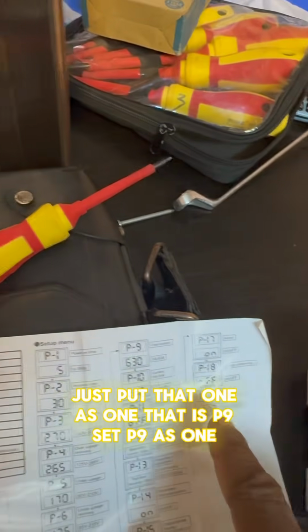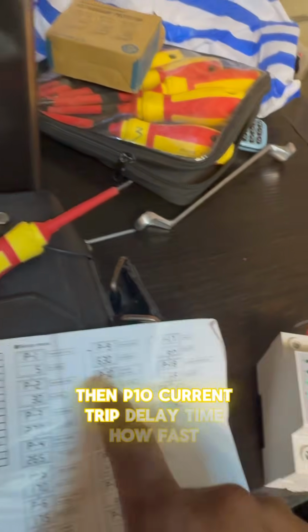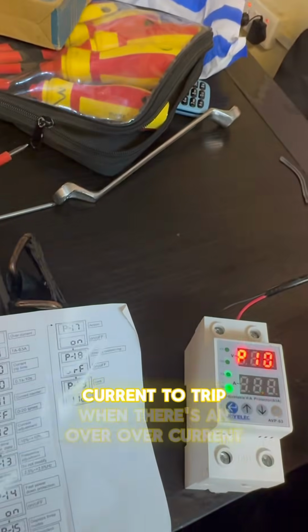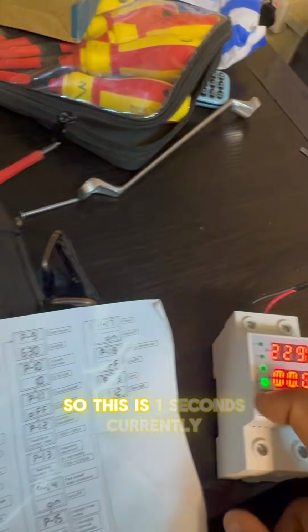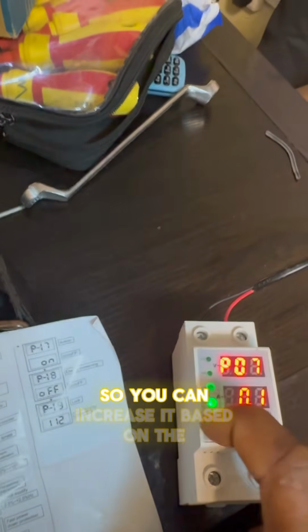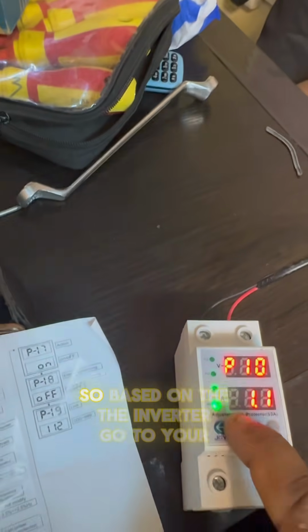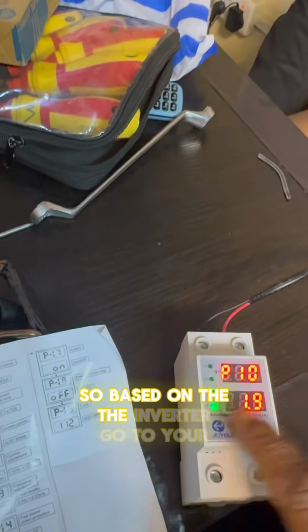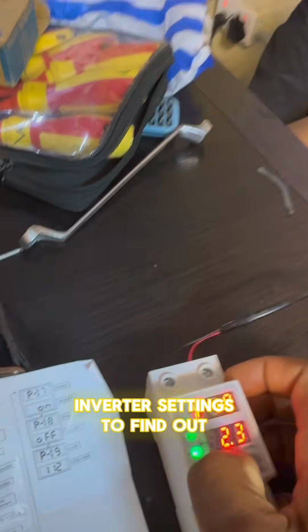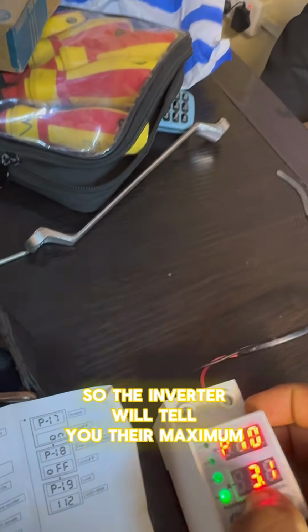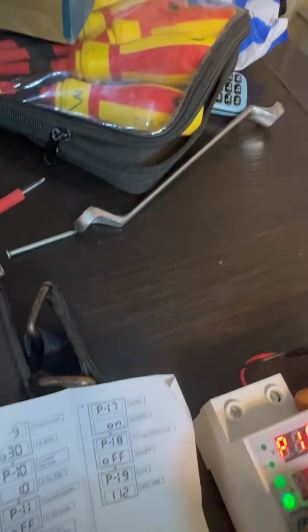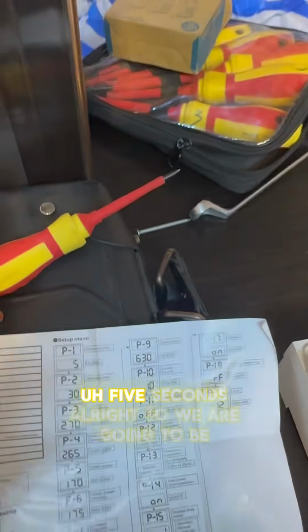All right. Then P10, current trip delay time. How fast do you want this current to trip when there's an over current? This is in 1 second currently, so you can increase it based on the trip delay. Based on the inverter, go to your inverter settings to find that. The inverter will tell you their maximum surge capacities. So we are setting it to 5 seconds. All right.